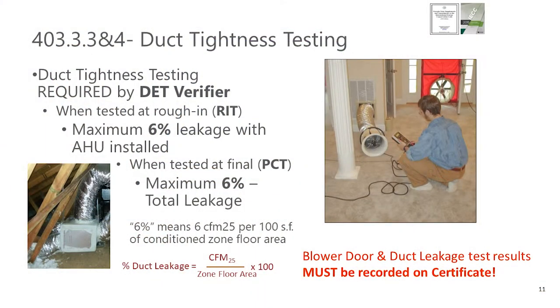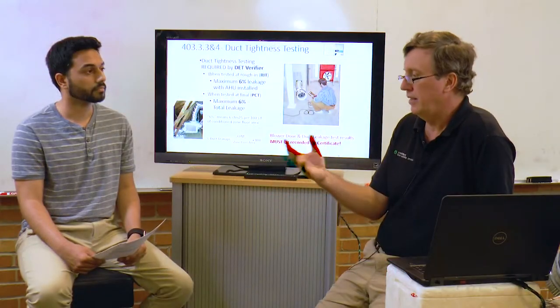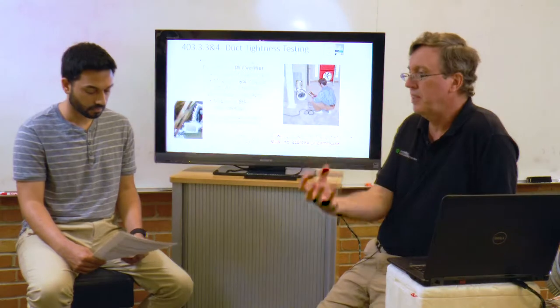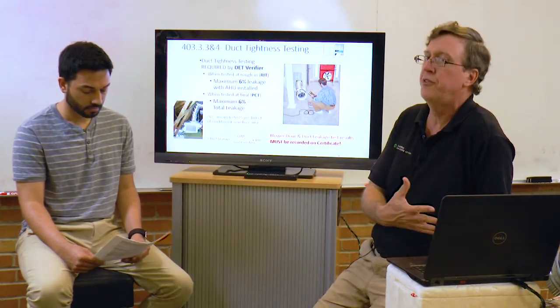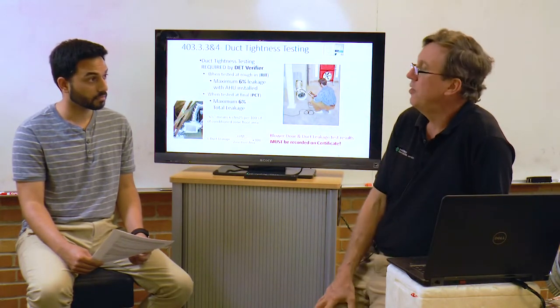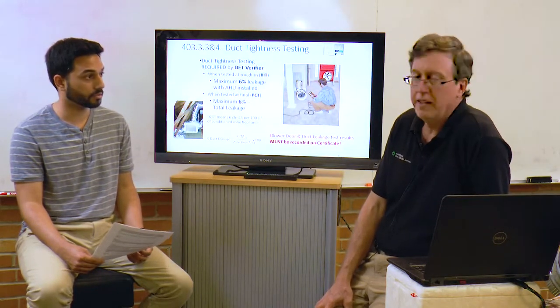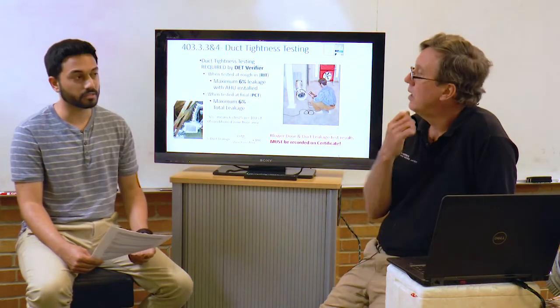You mentioned 6% duct leakage. Can you elaborate? Yeah, we say 6%. It's kind of a convenience. What the code language is actually saying is you're allowed 6 CFM of measured duct leakage at the test condition, which is 25 Pascal. So you get 6 CFM for every 100 square foot of zone that is served by that duct system. And the passing results are still recorded on the certificate. That is correct. What about the exceptions to duct testing?